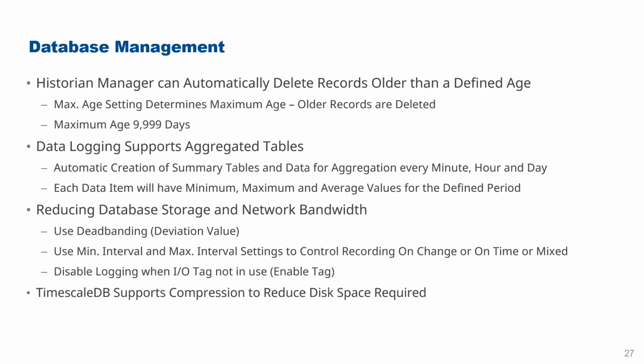Another option is to set the maximum interval setting. Again, if there are no changes over a particular time, you can set the maximum interval, and this will record at that maximum time. So if there's not much changing, you can make sure that you at least log some values at some time. This can be useful for 21 CFR 11 applications, where you might want to record at some times regardless, just to make sure that you are recording all the parameters. But again, it's a great way of reducing the amount of network bandwidth and the amount of data storage you need.